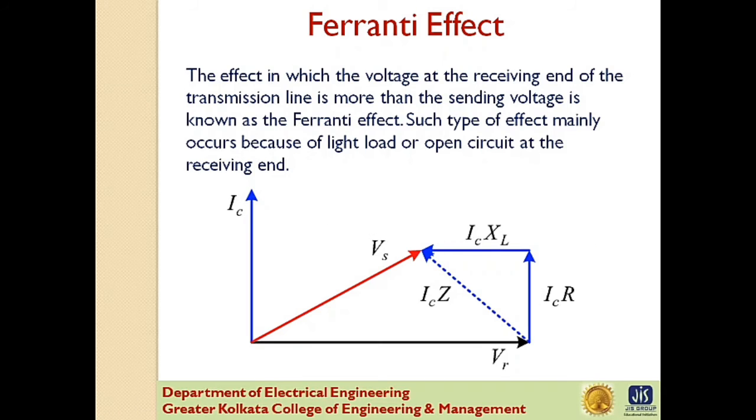The Ferranti effect. The Ferranti effect is a phenomenon that describes the increase in voltage that occurs at the receiving end of a long transmission line relative to the voltage at the sending end. The Ferranti effect is more prevalent when the load is very small or no load. The Ferranti effect can be stated as a factor or as a percent increase. Now, what is Ferranti effect? The effect in which voltage at the receiving end of the transmission line is more than the voltage of the sending end, and this phenomenon is known as Ferranti effect.